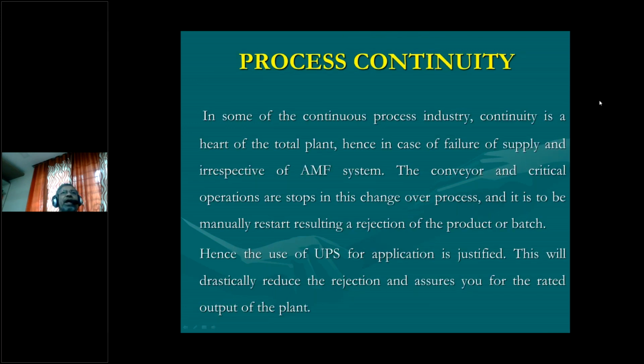That is process continuity. In some continuous process industries, continuity is the heart of the total plant. Hence, on failure of supply, irrespective of the AMF system, the conveyor and the critical operations are stopped during the changeover process and have to be manually restarted, resulting in a rejection of the product or a batch. When we work out any design, we discuss with the client to understand the application, the requirement of the industry and the process. In a chemical process, I forgot the name of that product because I'm not a chemical person, he told me that any stoppage of more than 10 to 20 seconds will make the viscosity go high and it will become a stone, and we would have to scrap that vessel also. So we need uninterrupted supply, not a single second of failure.